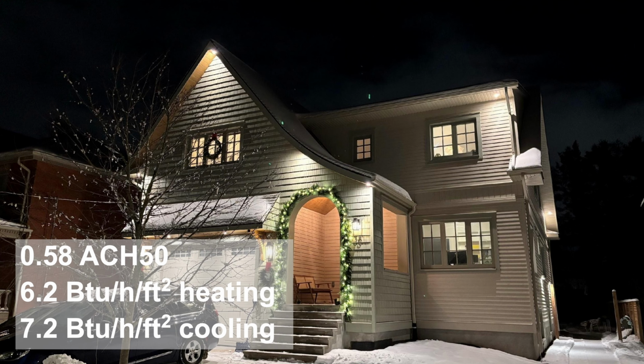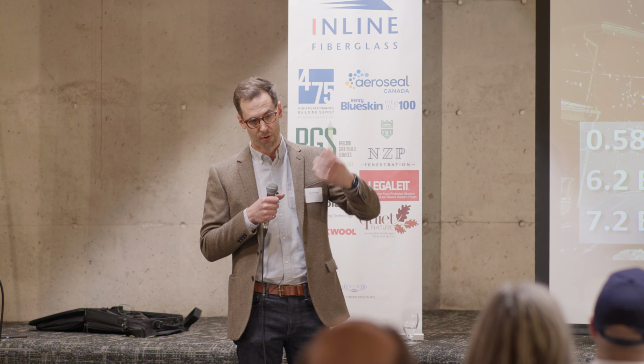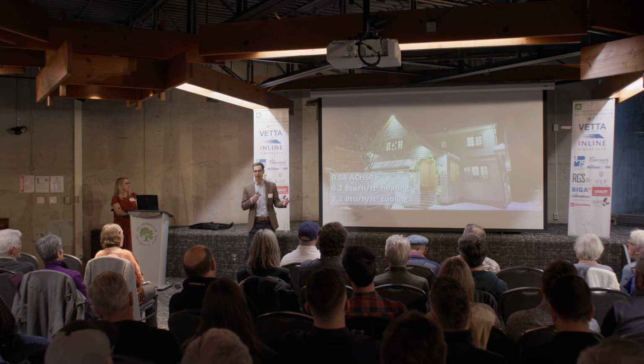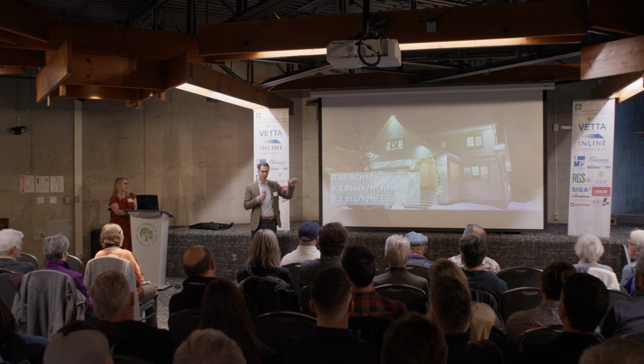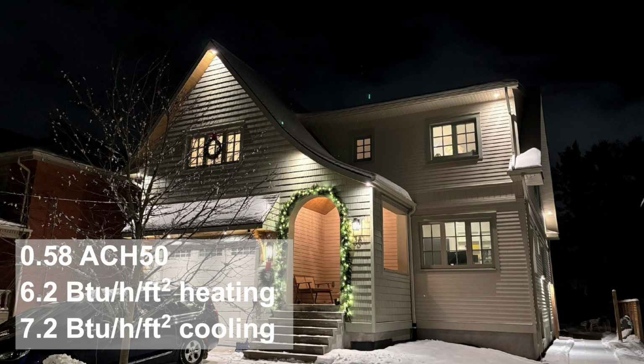We did a guillotine wood-burning fireplace with a chain-actuated flue damper. We have a direct air combustion duct going into that firebox with a damper. We have a direct vent range hood. I will die on that hill. It has a motorized damper on it, and it has a makeup air duct in it with a damper on it. And we hit 0.58 ACH50. The heating loads are 6.2 BTUs per hour per square foot and 7.2 in cooling, which I was pretty happy with. It's a 100% electric building, except for the wood-burning stove.